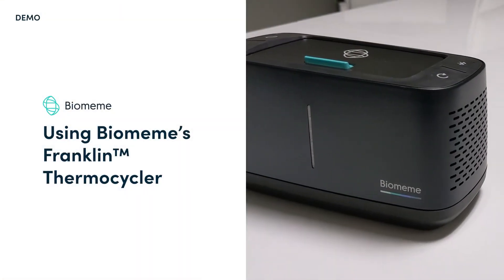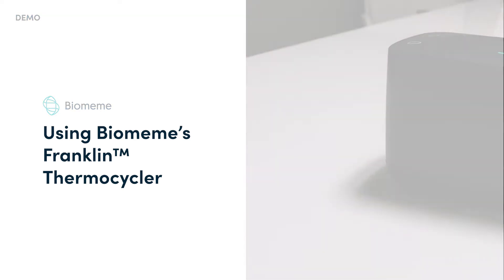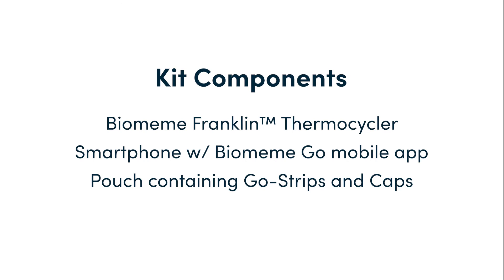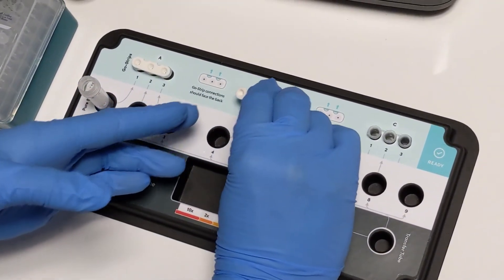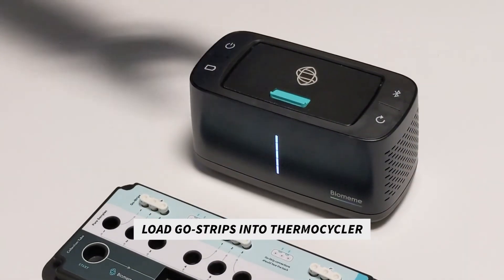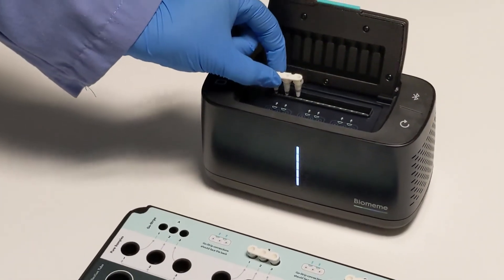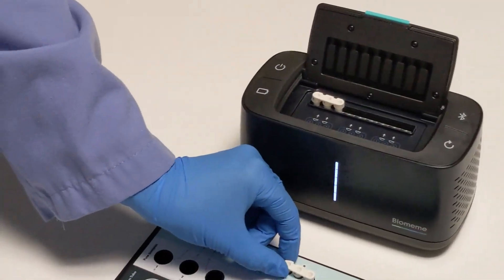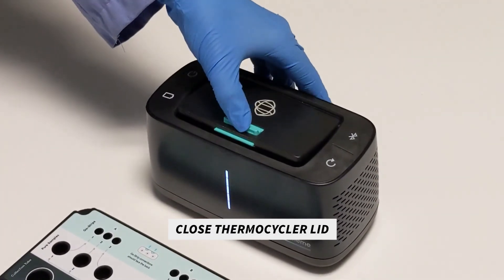Next up, we have Biomeme's third-generation manual thermocycler called Franklin. Step 1 is to once again gather the handful of items required to run a test. This includes a Biomeme Franklin thermocycler, a smartphone with the Biomeme Go mobile app installed, and a pouch of test strips. You start by carefully transferring purified sample into each well of each 3-well strip. Once all wells of the Go strips are filled, you gently place the void filling caps into each strip. Now, we open the lid of the Franklin thermocycler by pressing the latch on the top of the unit, and place each Go strip with the void filling cap inserted into each 3-well slot inside. We close the lid on the thermocycler and tap Start Run in the Biomeme Go mobile app.